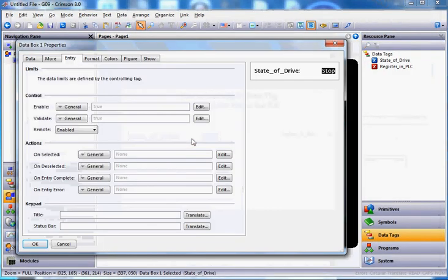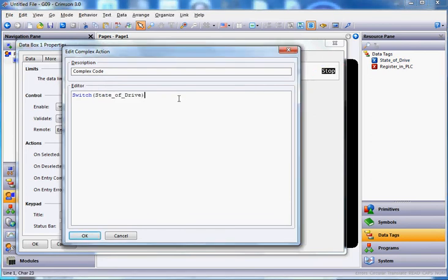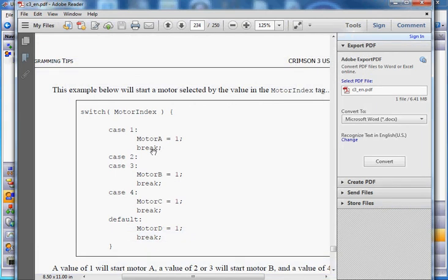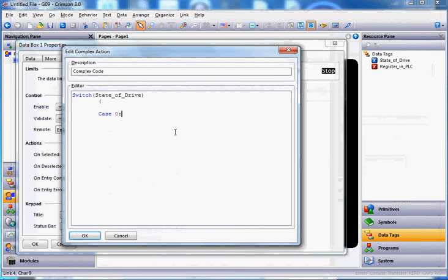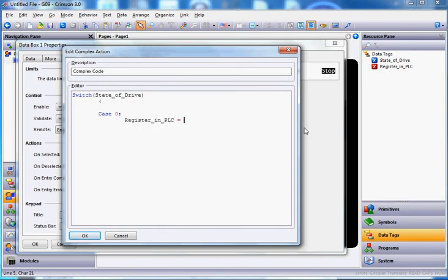Once again I'll double-click on the control. I'm already in the entry tab under entry complete. I'll hit the pull-down and go to complex. According to that example, I'm going to type: switch parentheses, then drag in the state_of_drive tag, close parentheses, enter, tab across, open bracket, enter. Then I'll type case 0: — meaning when this equals case zero — then drag in the register_PLC tag and set it equal to zero, enter, tab across, then break semicolon. That takes care of the first case.